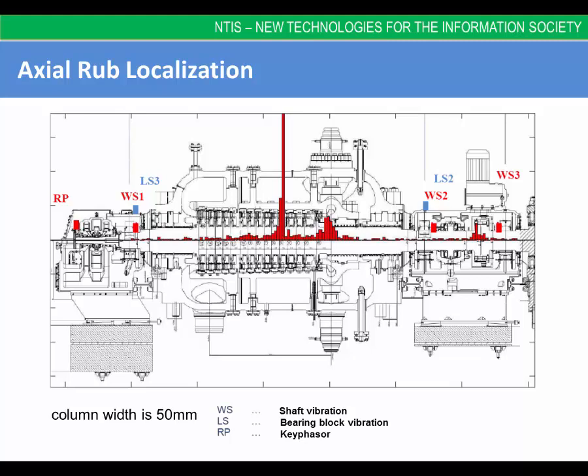In the picture you can see the resulting axial localization of the shaft rubbing in the form of a histogram. The histogram column width is 50 mm. The scheme of the HP part of the turbine is shown in the background and several rotating blade stages are noticeable in the figure. The measurement planes are also highlighted and marked. According to the obtained results, the highest occurrence of rubbing impacts was between the fourth and the sixth bladed wheel. The variance of the results is caused by noise in measured signals and also, as found by turbine inspection, the rubbing occurred at slightly different places depending on the operational deflection shape of the rotor.